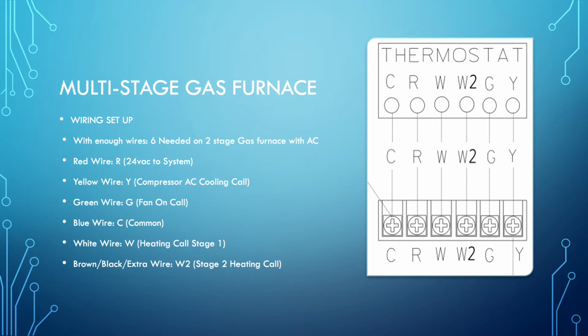First off, when you're doing the thermostat, presuming that we are going to control this from the thermostat, you're going to need at least 6 wires if they have an air conditioner attached to the system, which is most often the case. And it assumes, of course, that you need to have the common wire used on the thermostat. Now, red, this goes back to our previous video about the HVAC industry standards for what color wire goes where. There's only a few of the wires out of the bunch that really are a standard. After that, it kind of varies. But red is one of them.